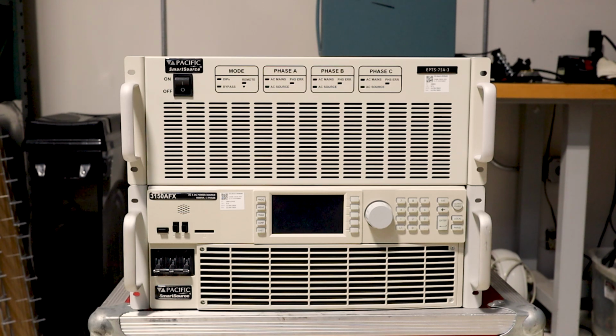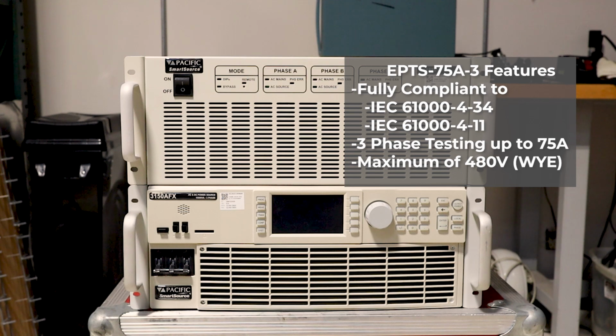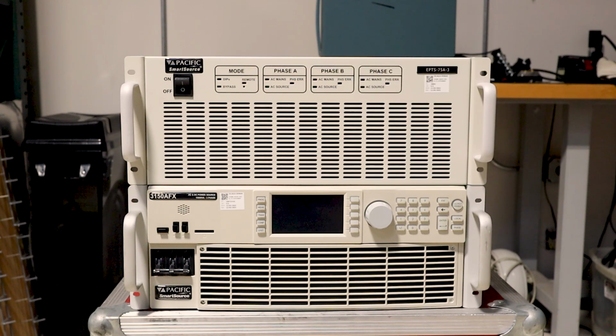The EPTS-75A-3 is fully compliant to IEC 61000-4-34 and IEC 61000-4-11 and is designed for three-phase testing up to 75 amps. It meets all the requirements for testing, including the rise and fall times. This system is limited to a maximum of 480 volts and is only designed for Y power. If delta is used, damage to the unit can occur. Let's go ahead now and take a look at the connections needed to get the system operational.